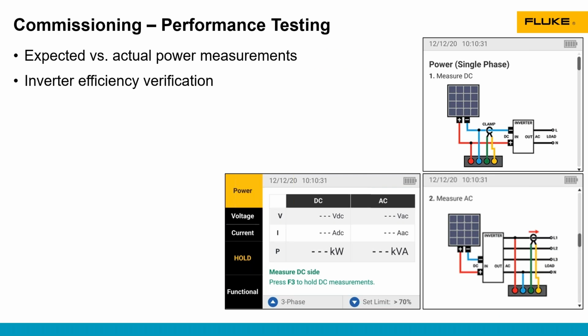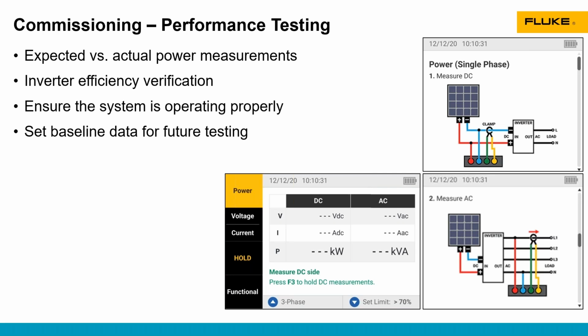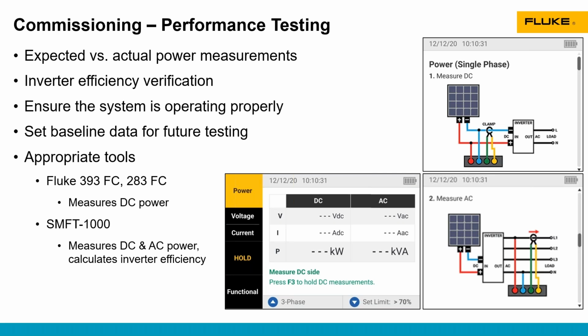We often do performance testing during commissioning, and many times this is done using the data acquisition system included with either the inverter or the monitoring platform installed with the system. We're making sure that our actual production meets what we expected. We can also use this type of testing to calculate inverter efficiency. We're making sure everything's working right. In that commissioning, we're setting that baseline for the future to know that everything was working the way it should have been when we started the system up.